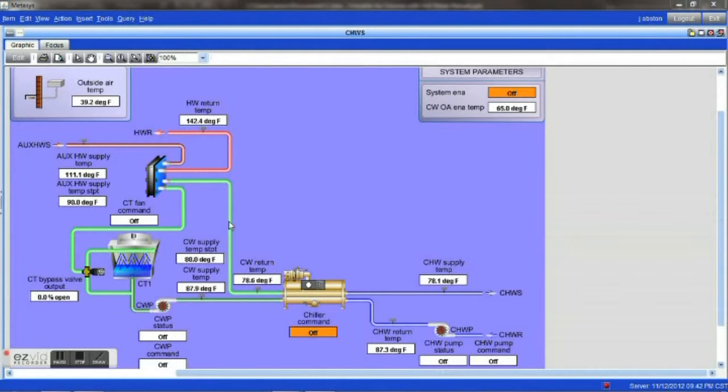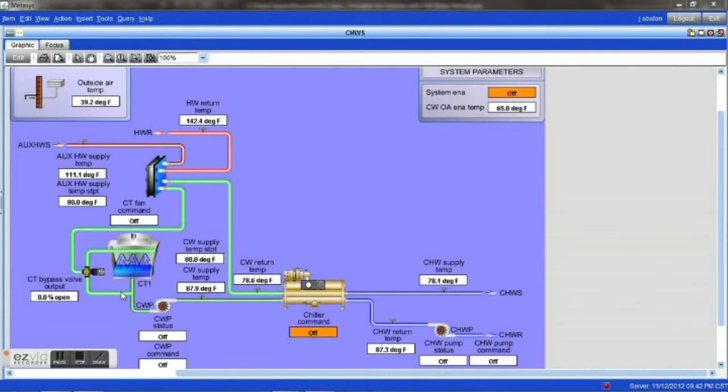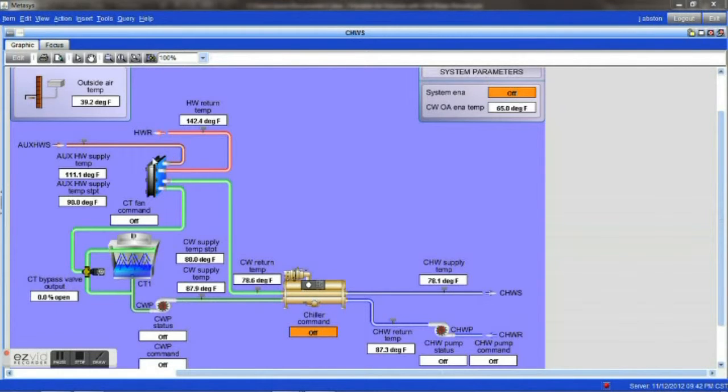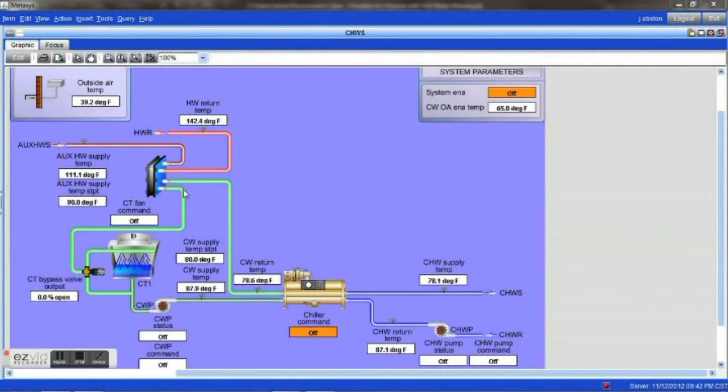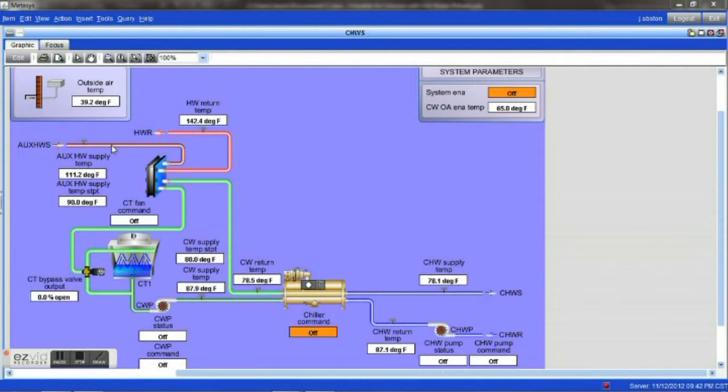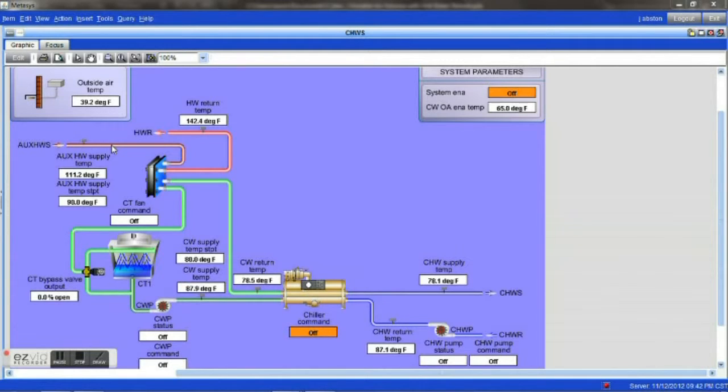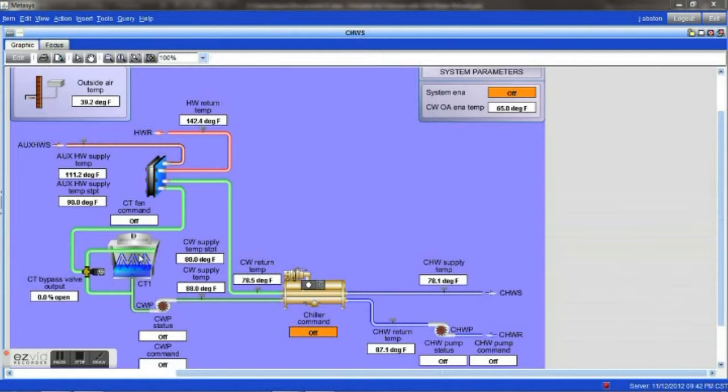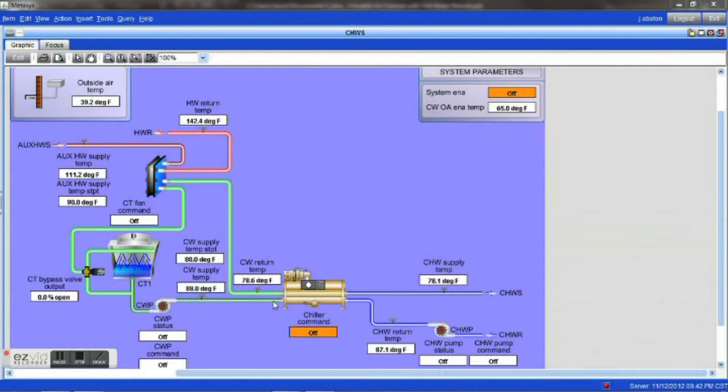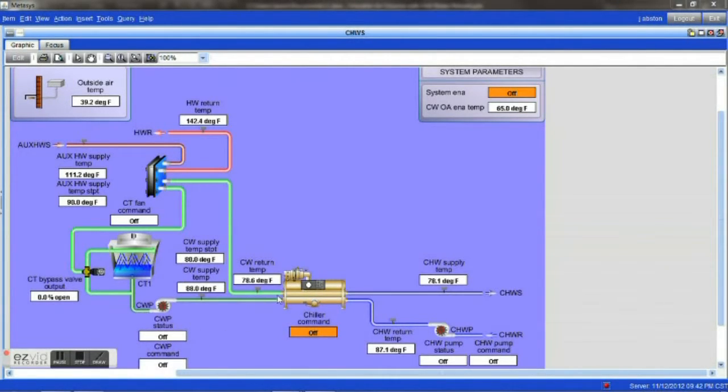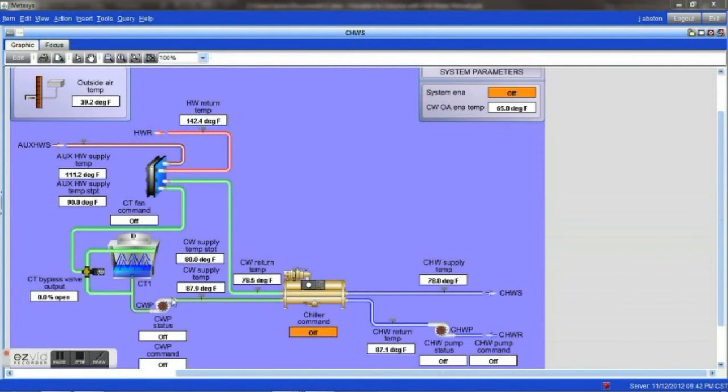So what we can do with that energy, instead of just dumping it over a cooling tower, which is exactly what happens in a lot of instances, we're actually, through a heat exchanger, a plate frame heat exchanger, going to recapture some of that energy. Use it to heat the water for our hot water system to serve our reheats. And then if there is any excessive energy, that heat will then be sent over the cooling tower to maintain the set point for the condenser loop of the chiller.